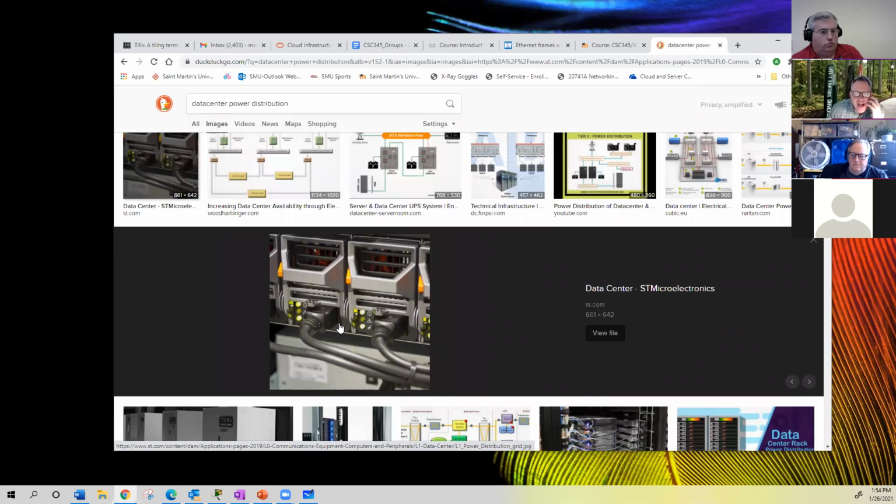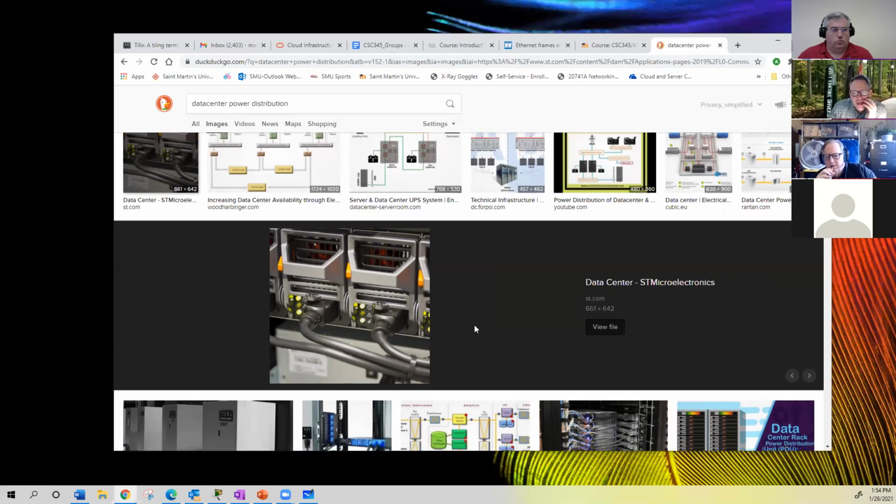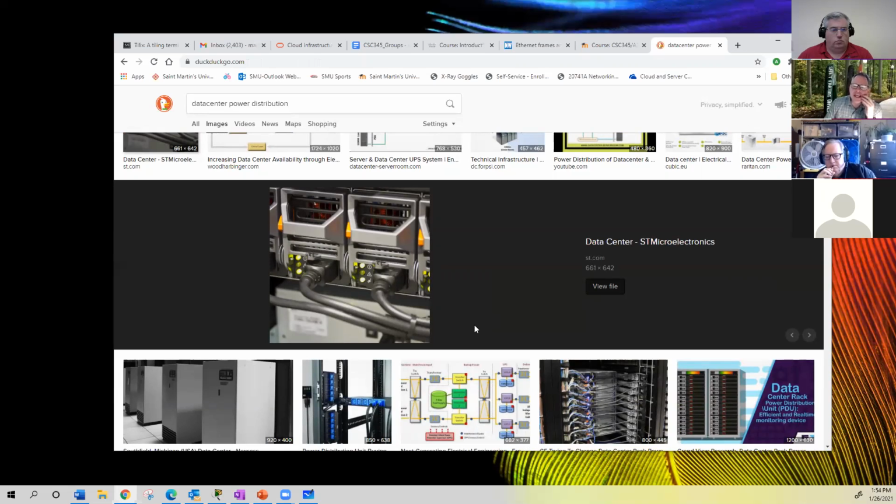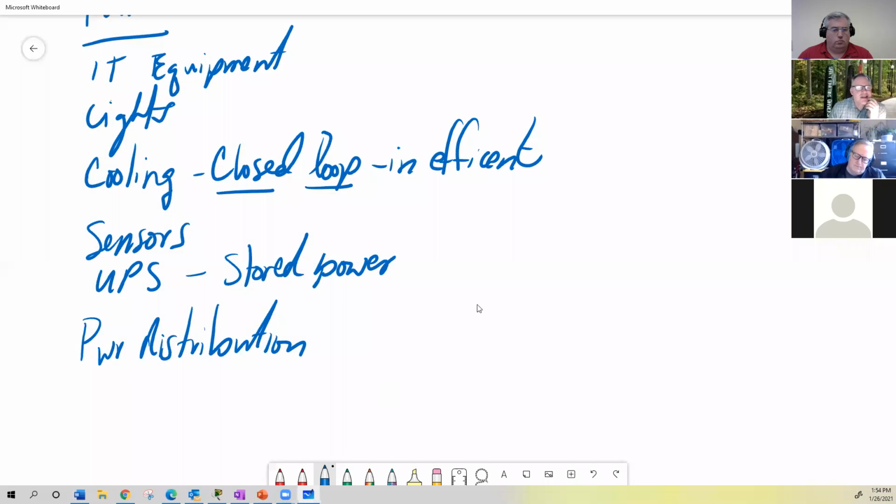They're 95% or 98% efficient. So your power supplies also heat up and lose some power to heat when it goes into your server, and it's used for memory. The motherboard, the processor is probably one of the biggest consumers of power in your server. Well, as those heat up, the hotter they run, the more power they consume too. It's called leakage in the silicon. So everything has this power loss in all of these steps.